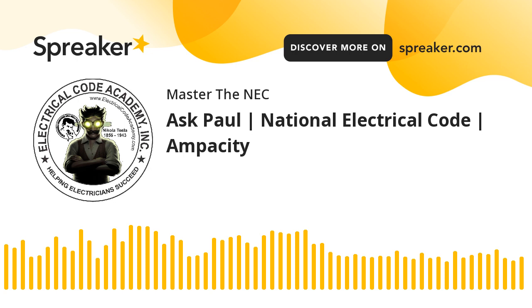All right, so when it comes to ampacity, the ampacities in 310.16 are continuous. All those amps you see, under the conditions of use, and we'll explain what conditions of use are, that is the ampacity of that conductor, whether it's copper or aluminum, at that temperature indefinitely.